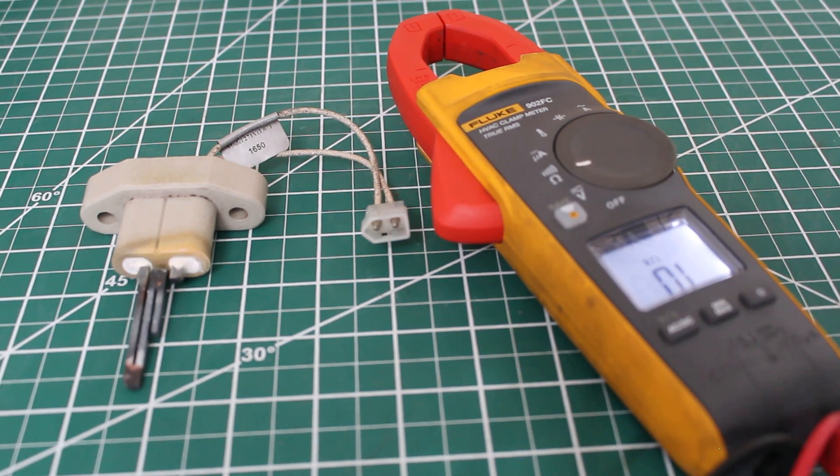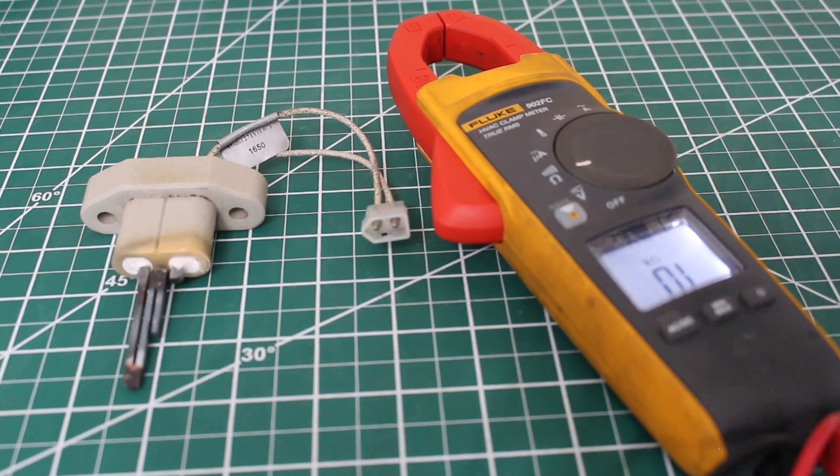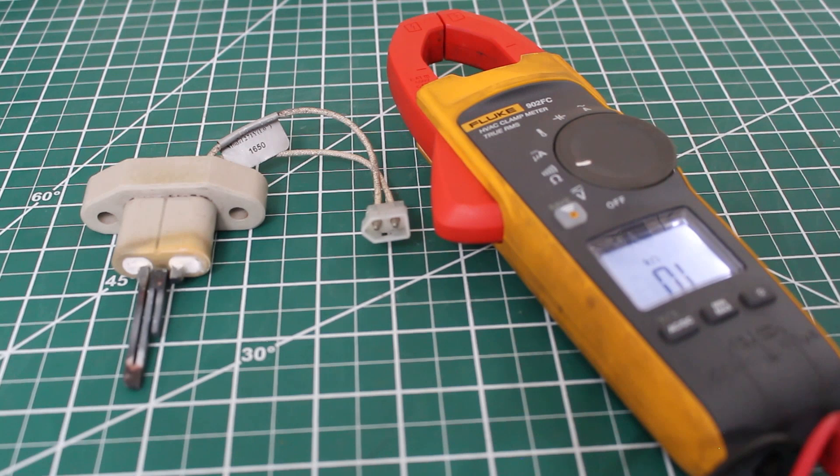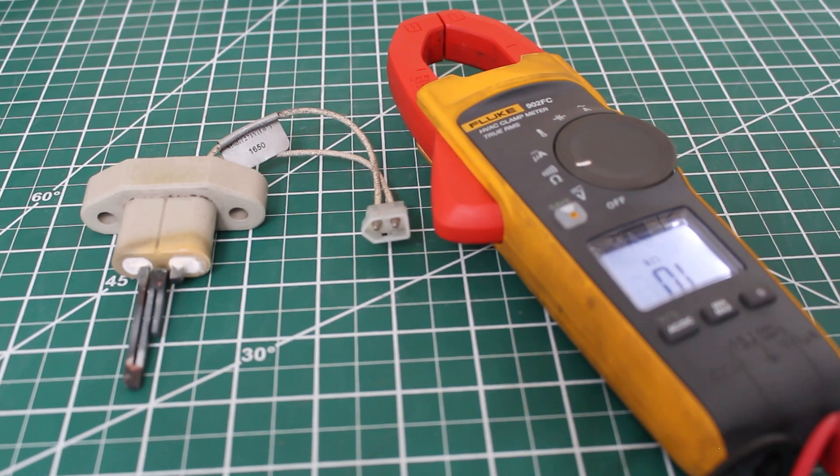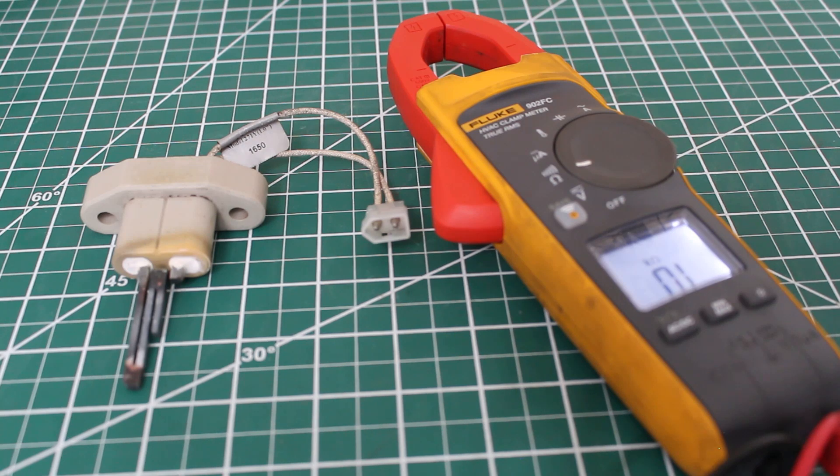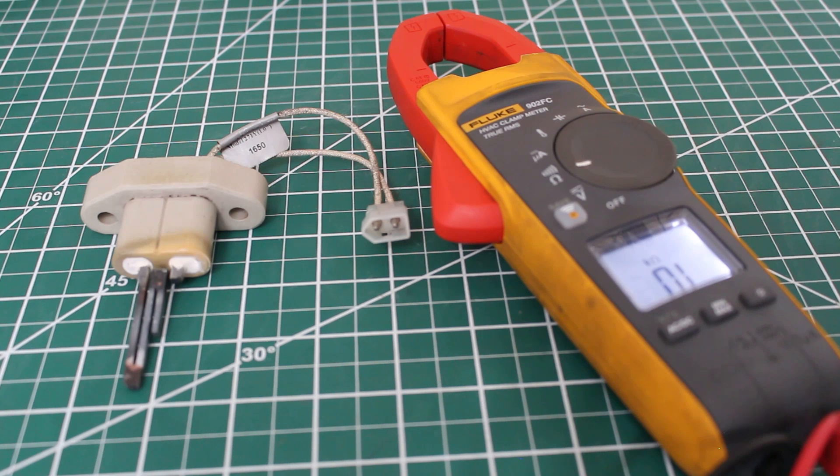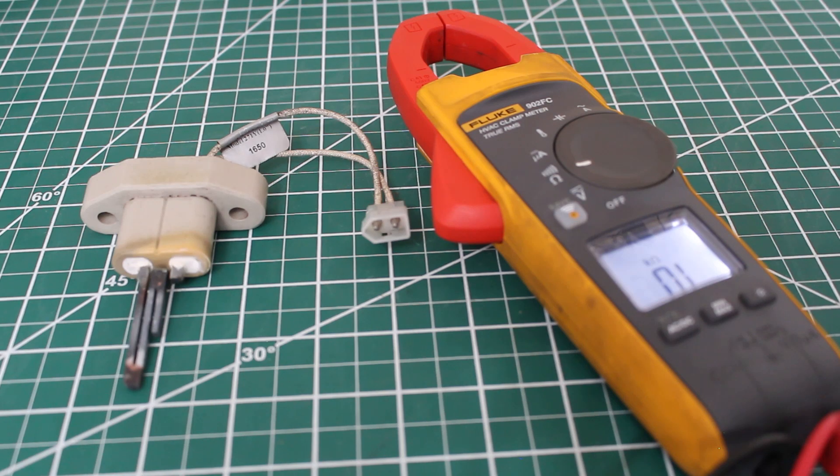Rule of thumb is you want to read anywhere between 40 to 90 ohms across your hot surface igniter. This all changes when it comes to the voltage applied and the style that you have. That's why this method is not really my preferred because those numbers could change. I feel that the only reliable method here is if you get an OL reading or not.